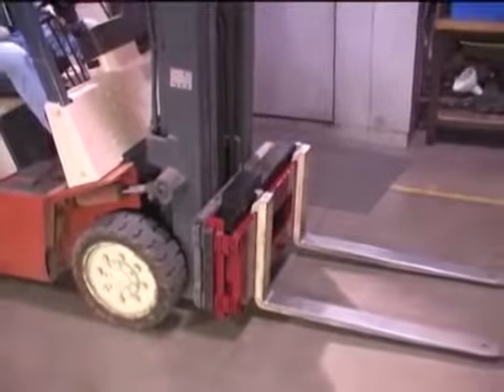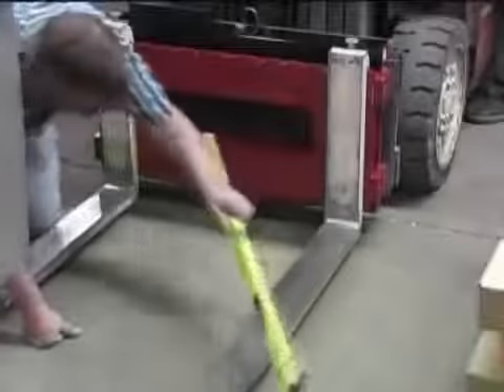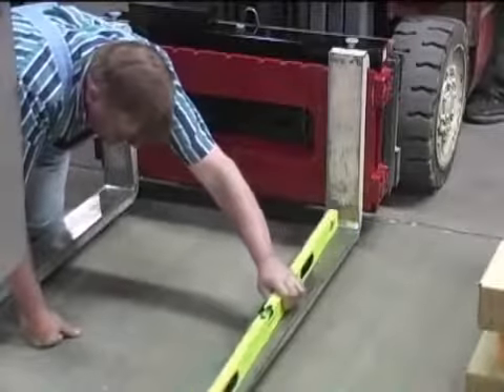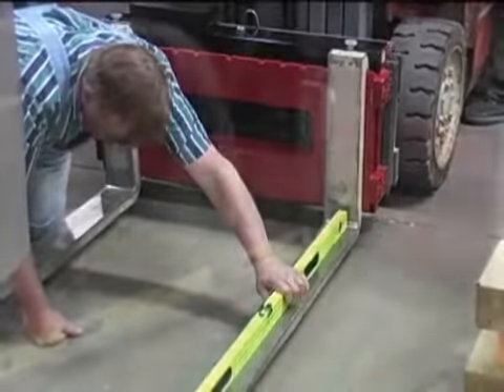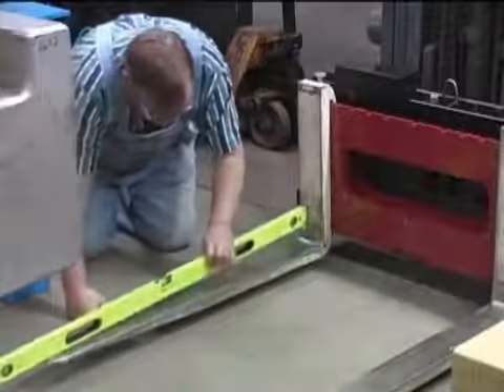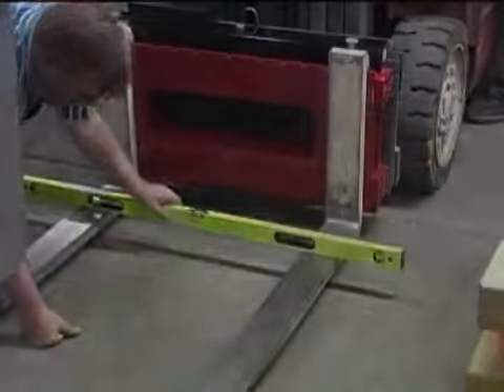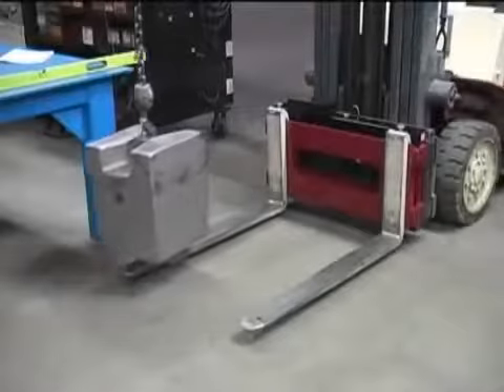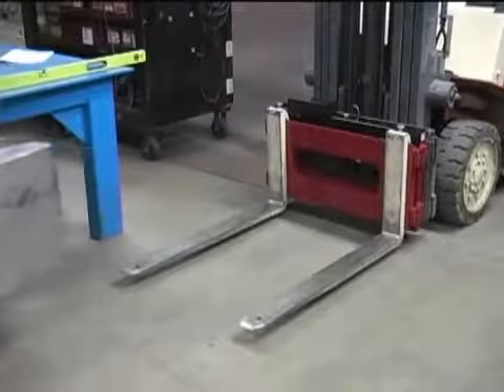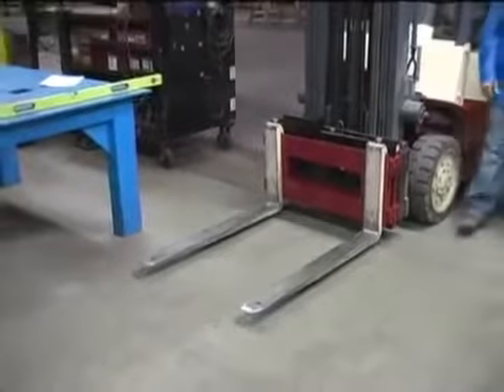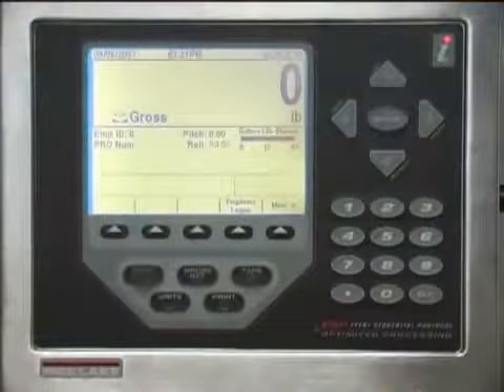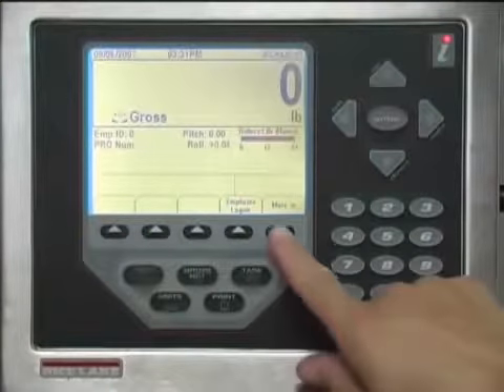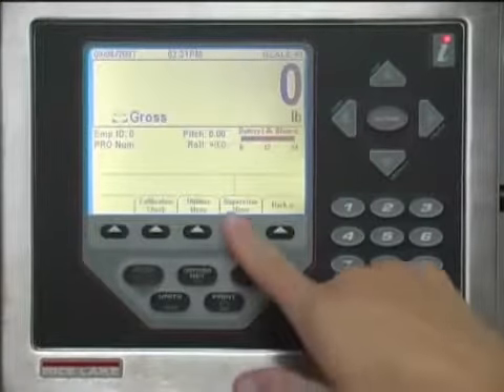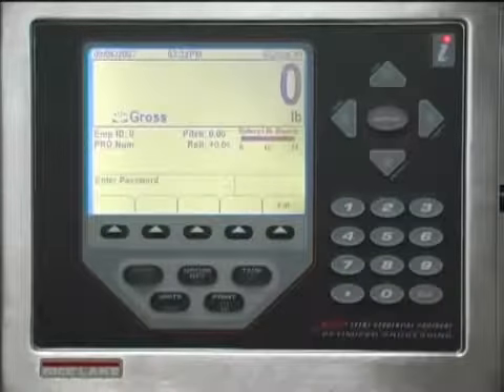The forklift tines must be in place as test weights will be placed upon them. Use a level to ensure the forklift tines are level from front to back, pitch, and side to side, roll, prior to calibration. The test weight used to calibrate the CLS cannot be greater than 2,500 pounds. With the 920i indicator in normal weighing mode, press the More soft key, then the Supervisor menu soft key. Enter a password if prompted.